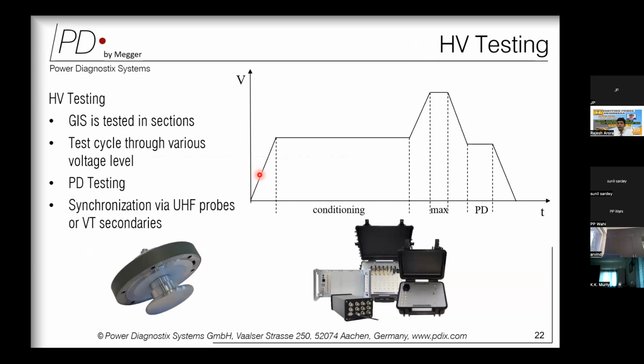discharge. The second important test in GIS is a HV test, because generally whenever GIS is tested, the sections are tested in the factory or in the site, because if we test the entire GIS, we need a very big power supply. Hence, it is always tested in section and it is passed through various test cycles. So the voltage is ramped, it is kept constant, called as conditioning of the GIS, and then it is raised to a maximum acceptable voltage of a GIS, kept there for some portion of the time, and then it is again reduced to a conditioning voltage, and then a partial discharge measurement is performed to check whether any PD is happening under the high voltage influence.